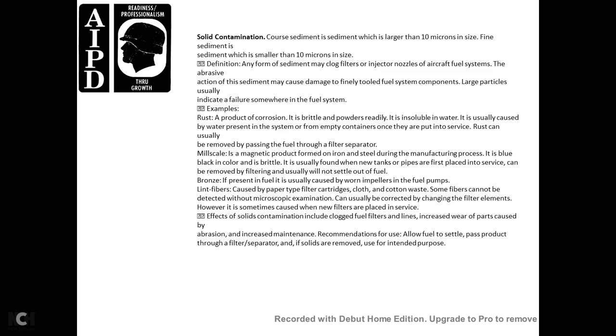Examples of solid contamination: rust — product of corrosion of brittle steel, usually caused by water presence in the system, and found in empty containers or newly placed-in-service equipment; rust can be removed by filtering. Mill scale — a magnetic product from iron and steel during the manufacturing process, blue-black in color and brittle, usually found in new tanks and pipes; it can be easily removed by filtering. Bronze — present in fuel and usually caused by wear from impellers in the fuel pump. Linen and fibers — caused by paper filter cartridges, cloth, cotton, or waste materials; some fibers cannot be detected without microscope examination and are sometimes caused when new filters are placed in service.